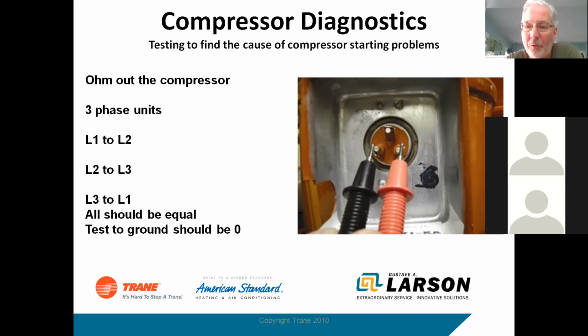On a 230 volt system, you may see a little higher, 1.1, 1.5, something like that. But if you're not sure, give us a call or look it up in the service facts. The ohm value is available for those units to make sure you have the proper ohm value. But again, three-phase is a little bit different.